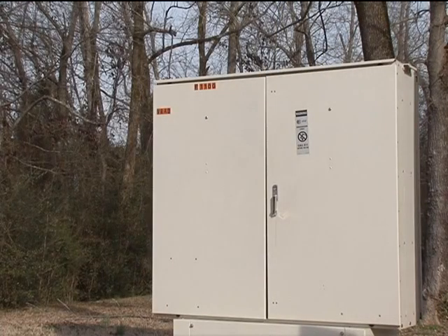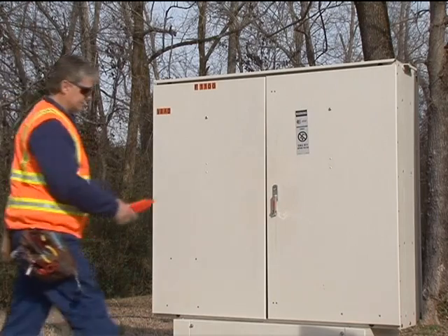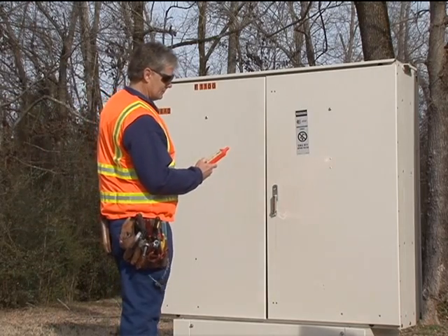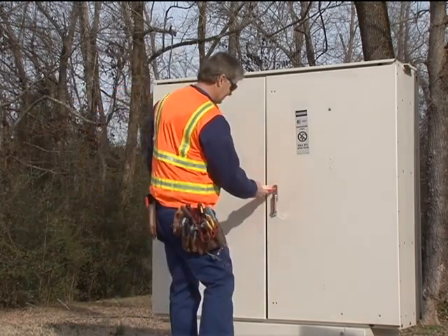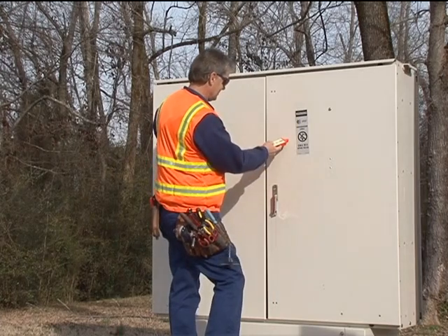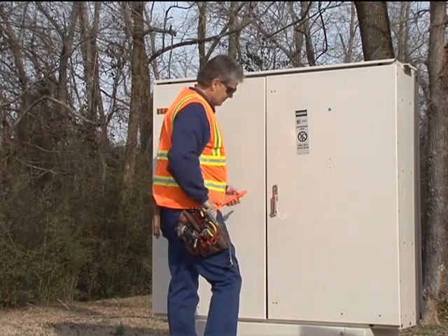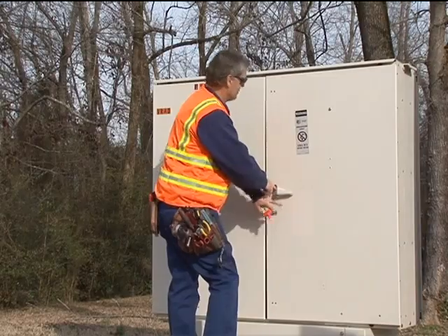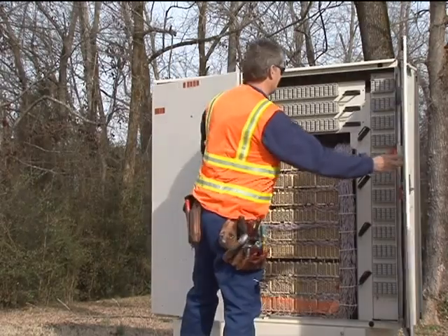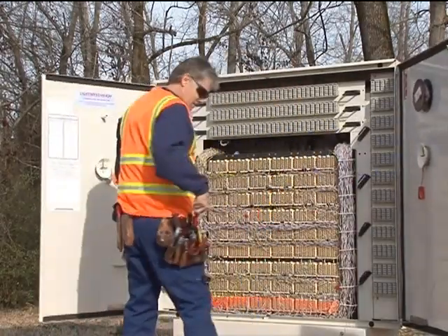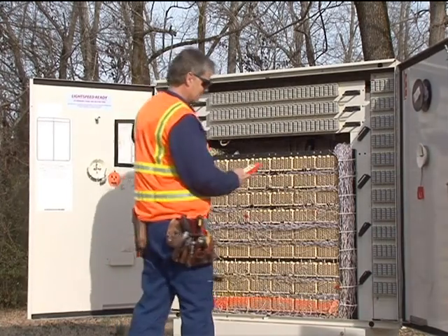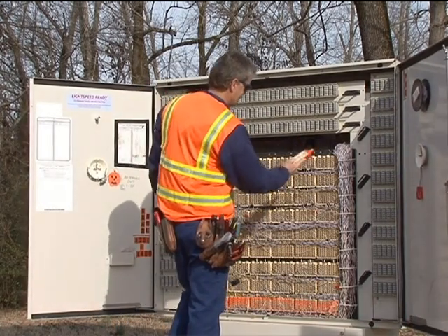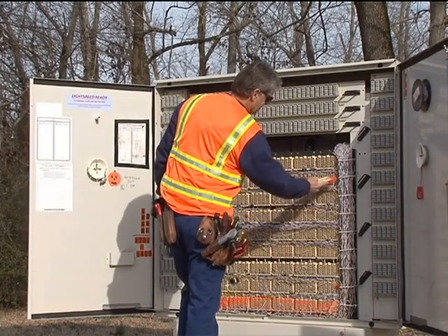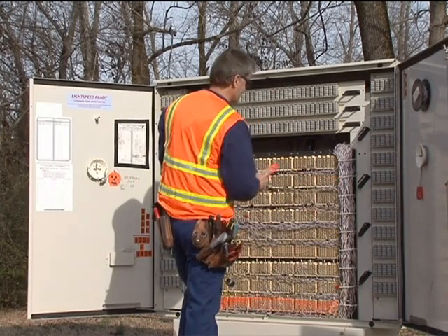To begin testing with the FVD, turn it on a few feet away from the object to be tested. When all of the bar graph steps deactivate and the green LED illuminates, point the probe toward the object and slowly move toward it with your hand holding the FVD extended out from your body. Continue toward the object to be tested until the probe tip touches the object. If the alarm sounds, more than 50 volts have been detected, and you must follow your company's safety practice.